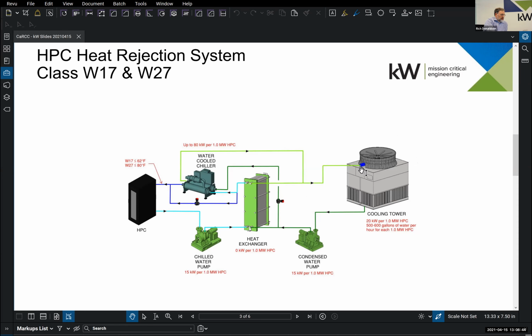Because this cooling tower can't provide us the temperature we need when it gets really warm outside, we would probably need some sort of a chiller to do some additional cooling. And then we need pumps to move that water in these two loops. If we look at the amount of power we need to cool this load, starting at the cooling tower, 20 kilowatts per 1 megawatt of HPC is a good benchmark. When that chiller is running, it could add up to 80 kW of power consumption. And these two pumps are going to be at 15 apiece.